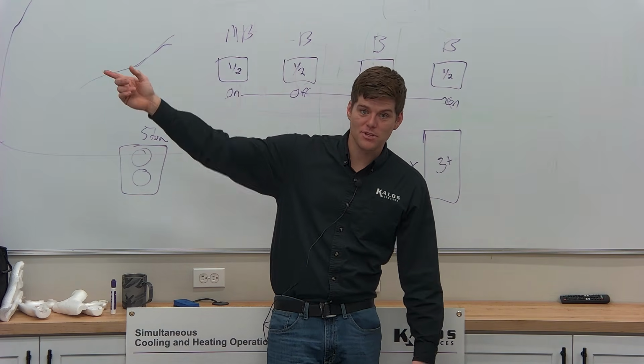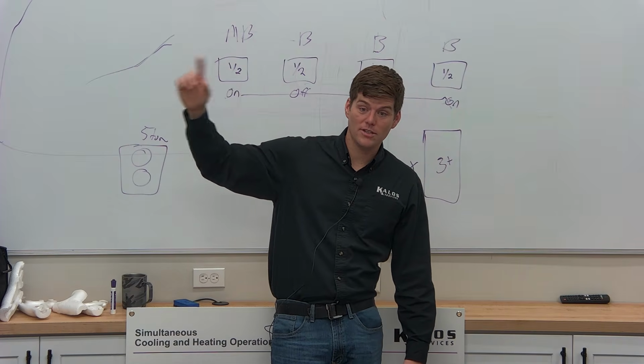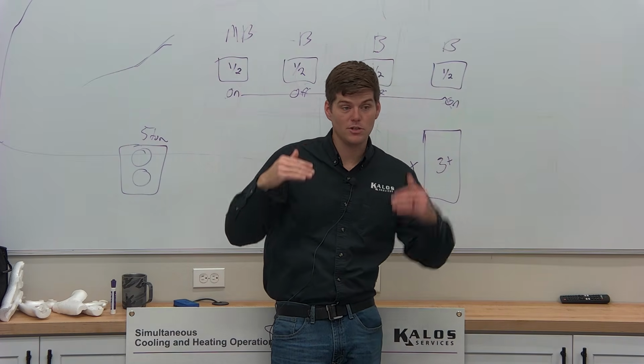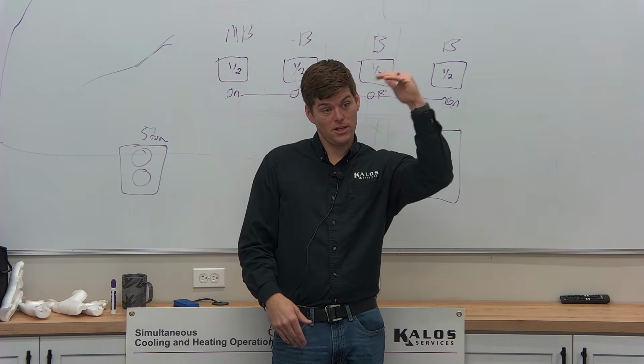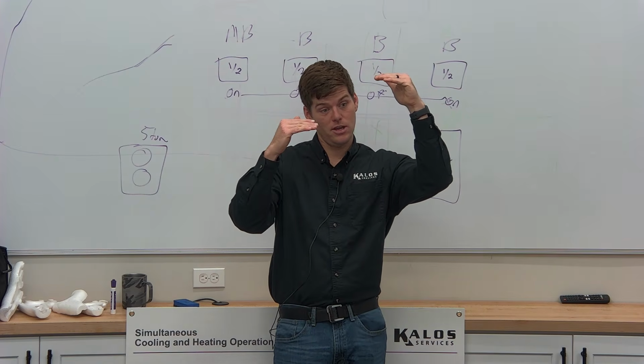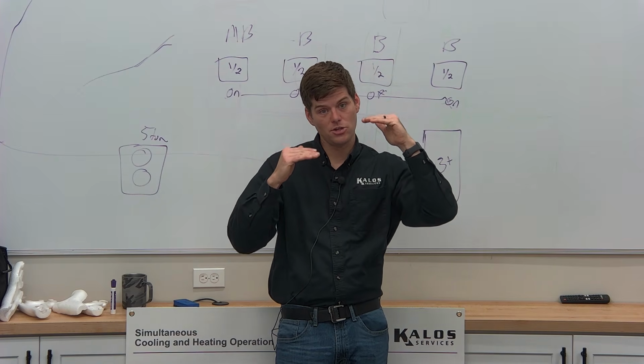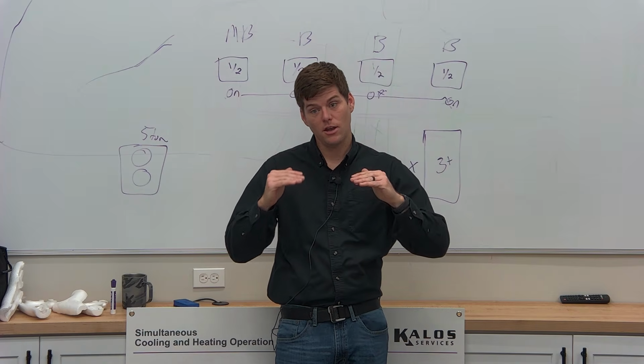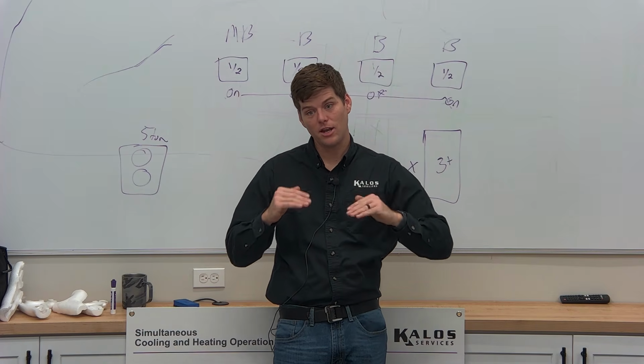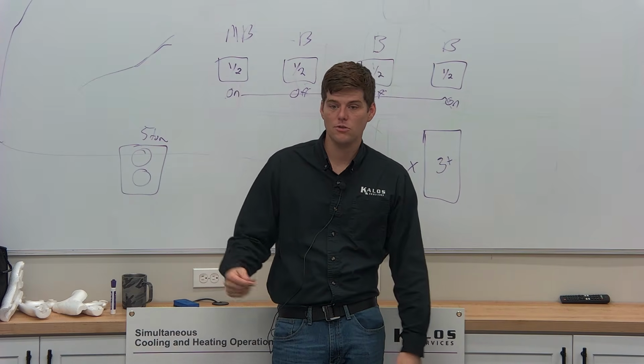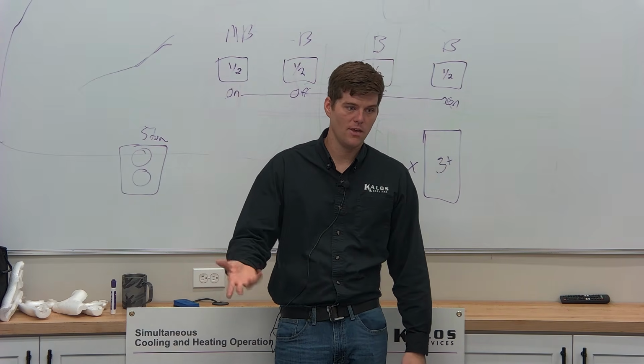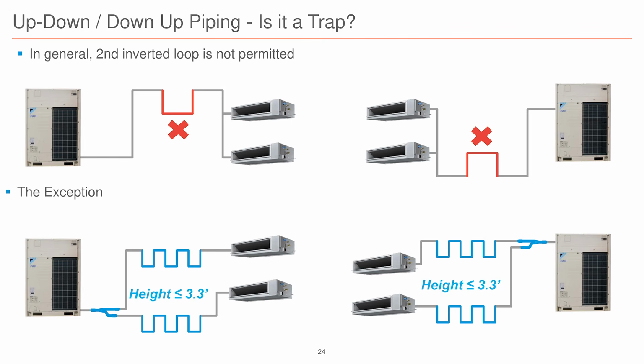But when you add traps to the system, guess what? Now it doesn't get that oil back like it's supposed to. And so when it's doing that calculation, it thinks oil levels are here when oil levels are actually here. And so as it gets lower in the calculation, then you run unlubricated, unlubricated, unlubricated, and then it goes into oil return mode, and the damage is already done. And you do that, rinse and repeat 10 times a day, and that's how you lose compressors. Traps are what kill compressors, and that's because of oil. The more complex the system, the longer the runs, the more detrimental something like this is.